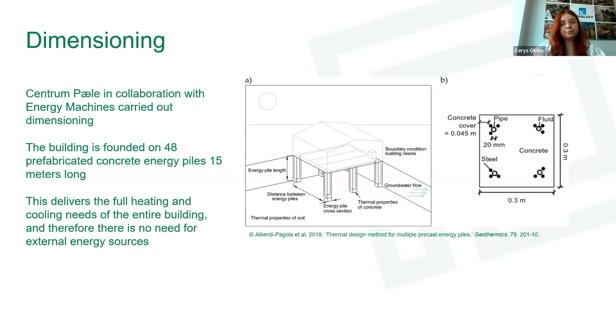So as mentioned earlier, one of the key design elements within this whole system is the optimization, the connection from the pipes to the manifold itself. And there's a consideration here to achieve hydraulic balance throughout the system and maintain its pressure, and also ensure the least possible heat loss when the system is active. And in Kollanda, it was decided that the prime solution was to connect the pipes in series and run those up to the manifold. So you can see on this picture here, there's not 46 pipes. These have all been connected in series. And that was done to reduce the size of the manifold itself, just to optimize space. And the pipes are laid on a layer of sand, just to maintain thermal conductivity, before the slab is then cast on top.